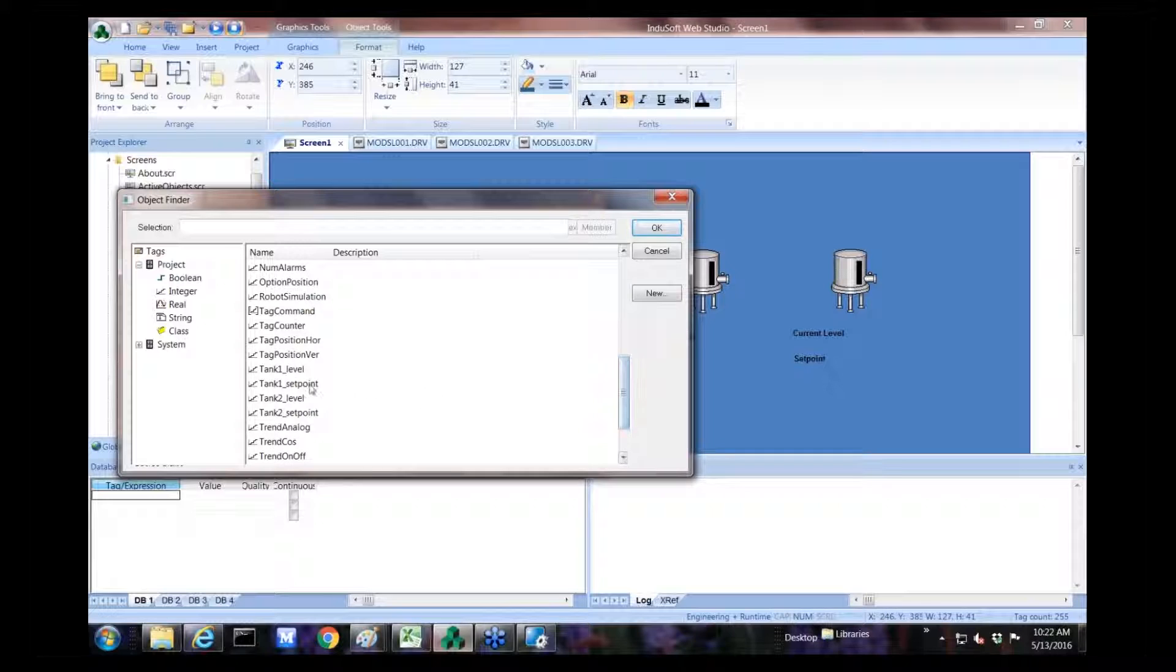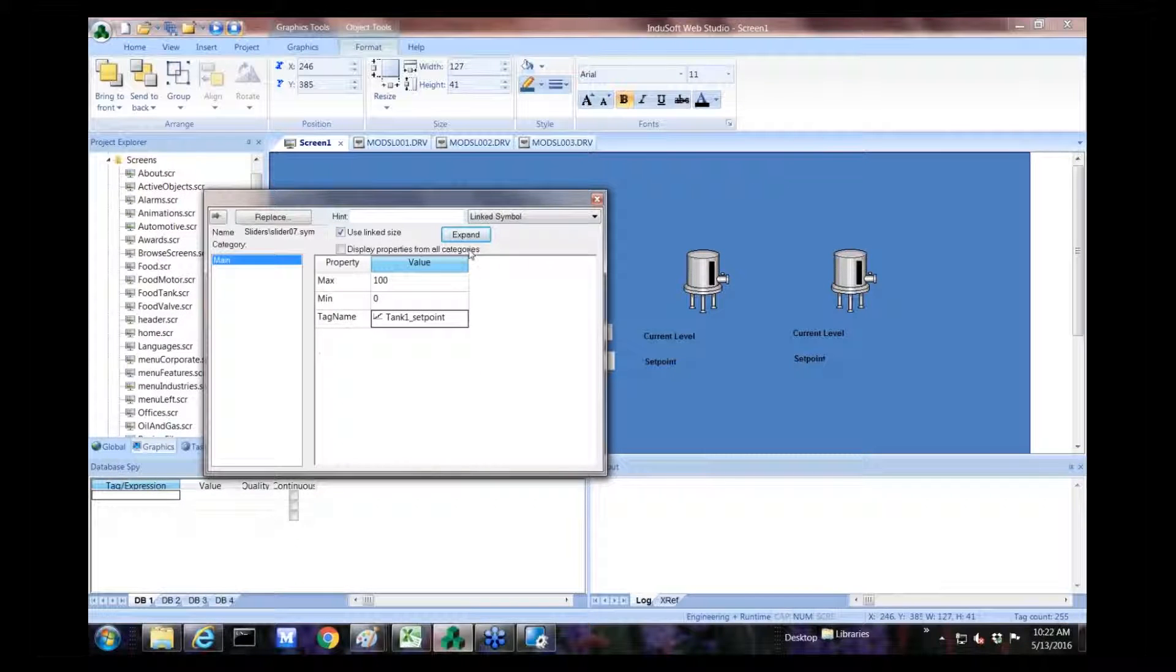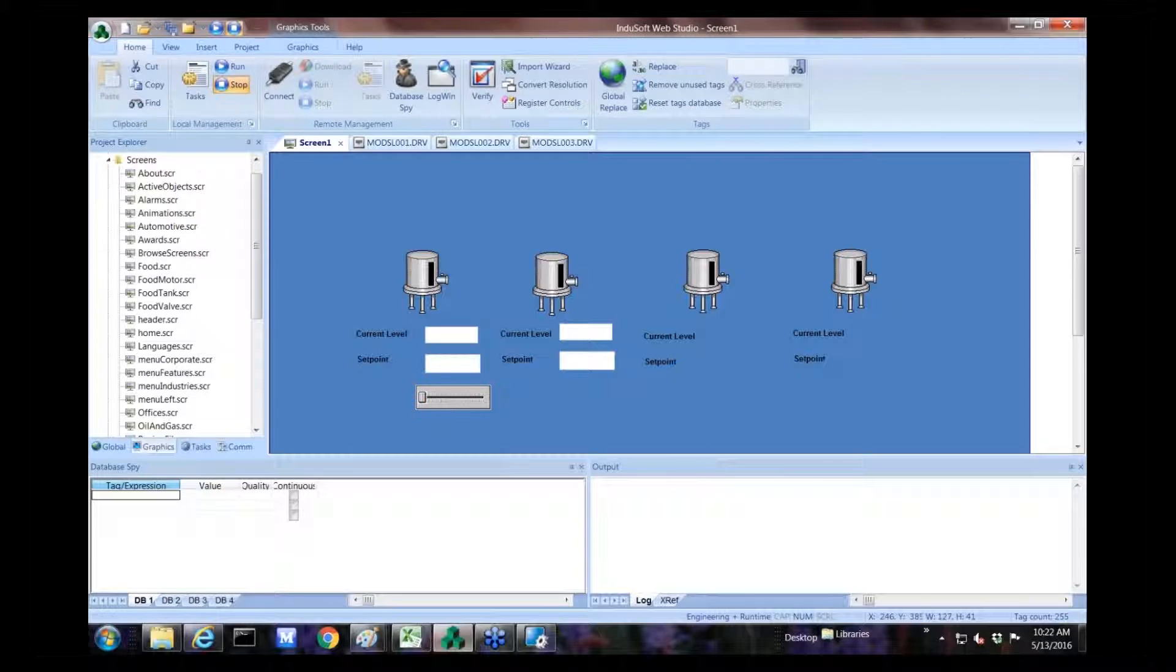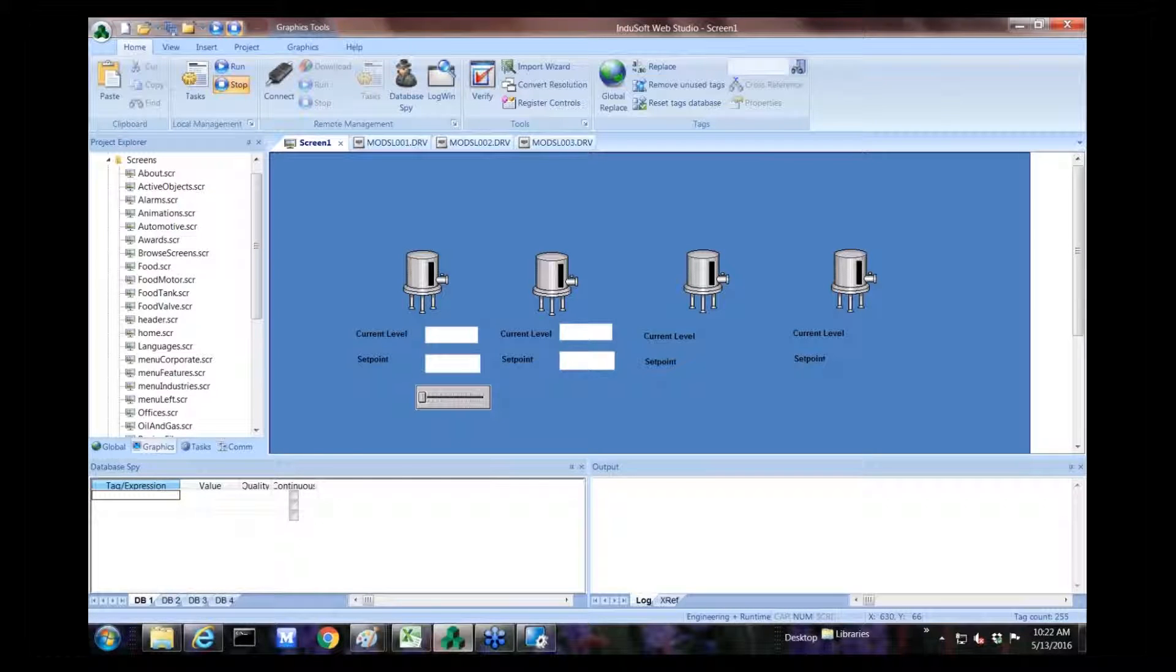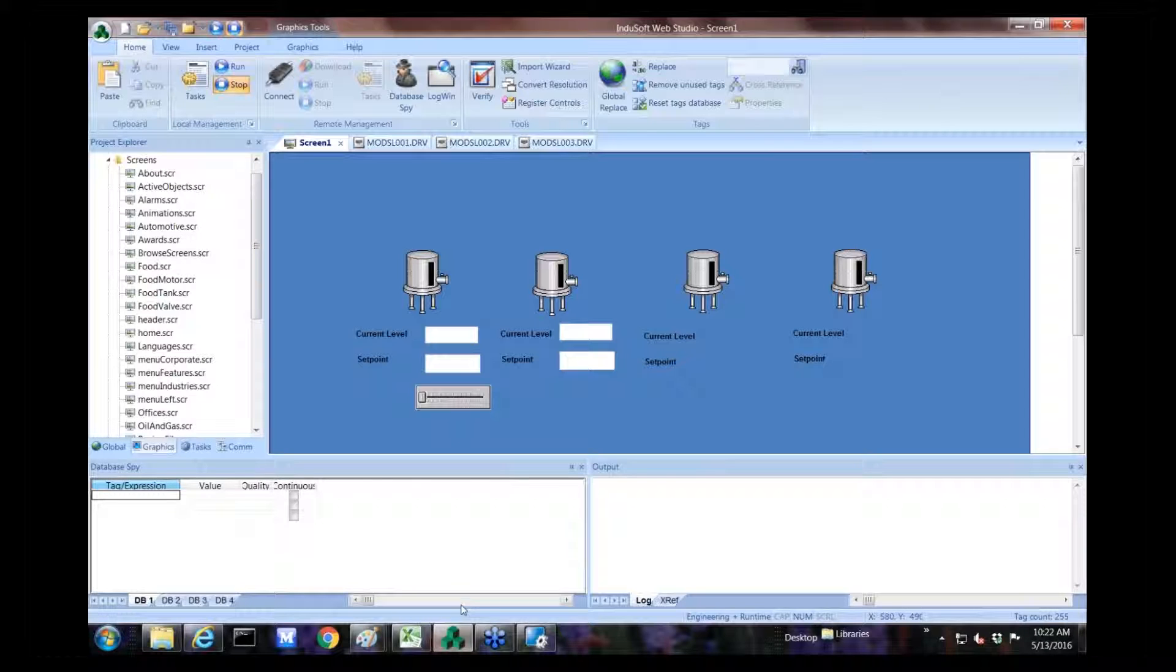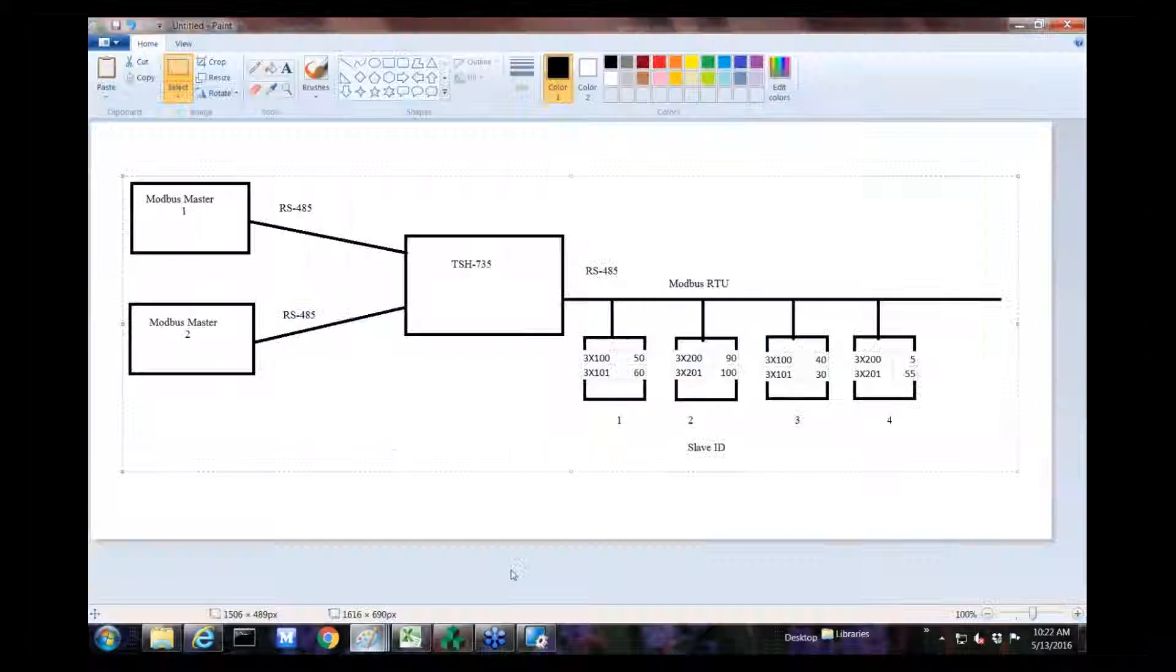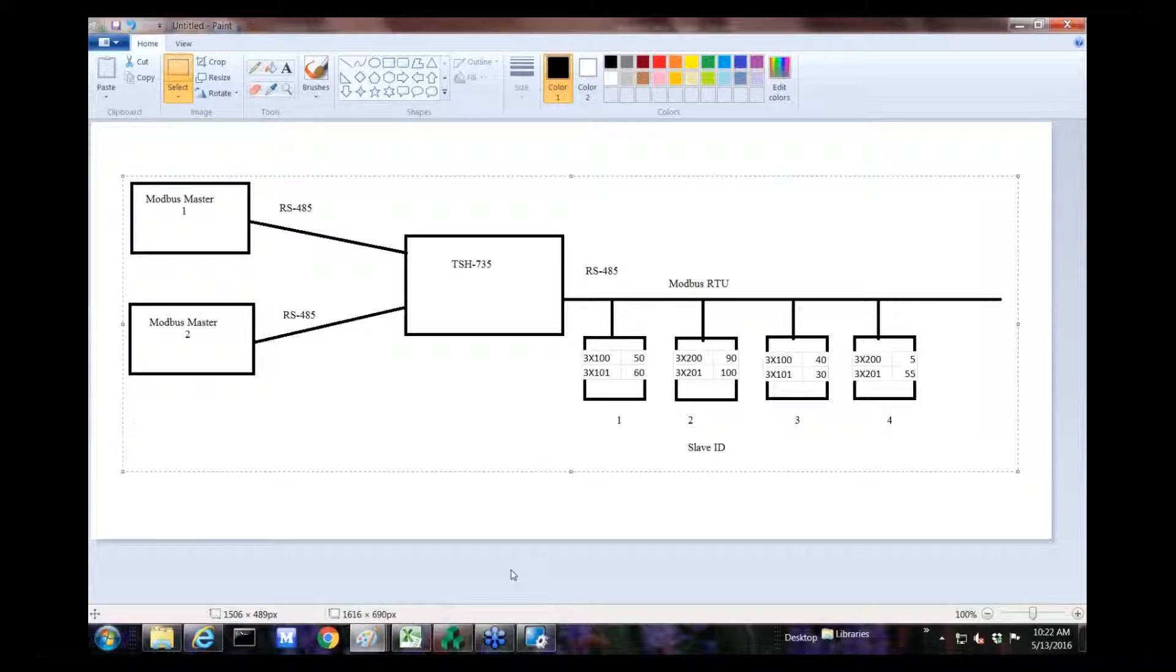That's all I have for you. But if anyone has any questions, I'd be happy to show them anything on the TSH or the Indusoft or the touchpad program in HMI works. The TSH is a Modbus sharing device, so it can allow two masters or multiple masters in this case to connect to the same device or same Modbus slaves. And you just connect them as if there's only one Modbus master. But the benefit is you can connect multiple Modbus RTU masters to a single set of Modbus RTU slave devices where normally you're only allowed one.